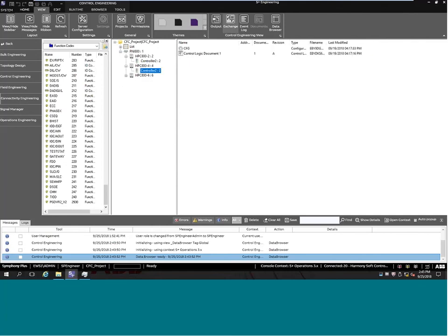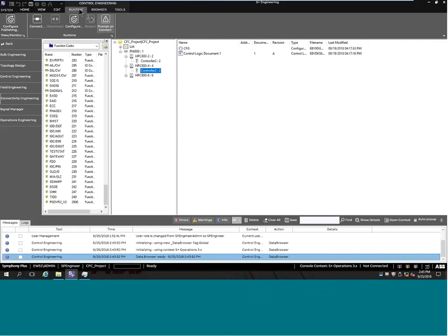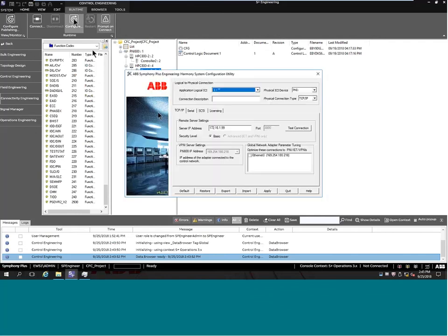All right. So that's how easy that is. I mean, there is some configuration setup, as Chin had said, in the Harmony API. So if you look down here, number 20 is considered Harmony Soft Controller, and we have a new physical ICI called Harmony Soft Controller, HSC. So this is all you got to do. You set this up, you tell it what computer it's running on, and it's running. It's that easy. You can run one soft controller on each engineering workstation.